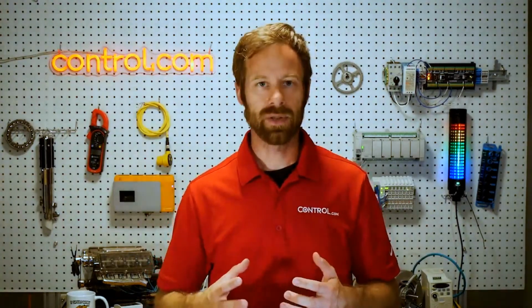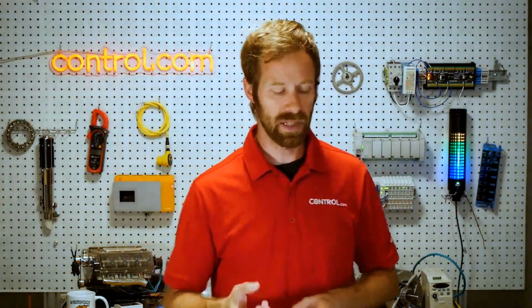So are there any advantages to this over discrete sensors? I think the answer is probably pretty obviously yes. We can have an analog sensor that can accomplish a lot more than a discrete sensor, but we do have to remember that they take extra modules, or if they're built in, they're going to be fewer built-in analog input modules for a PLC, so they tend to be more costly in a system. Instead of simply having one address in the PLC devoted to a trigger that's on or off, very simple, very easy to diagnose, we have to do everything manually in the programming when it comes to analog sensors. And sometimes that can create a much more complicated program, or unnecessarily complicated if we don't need it.